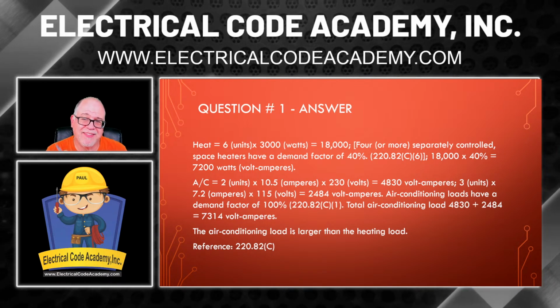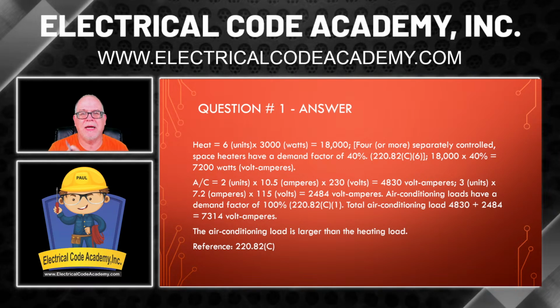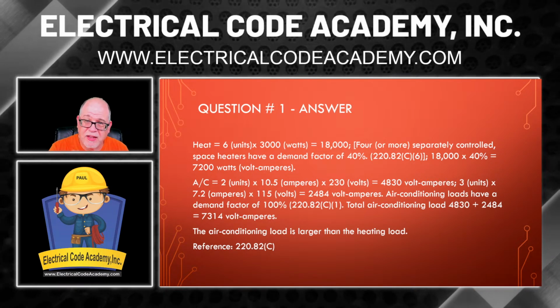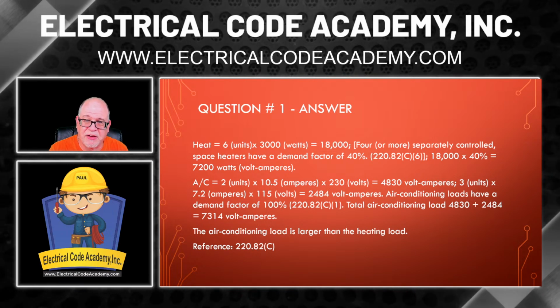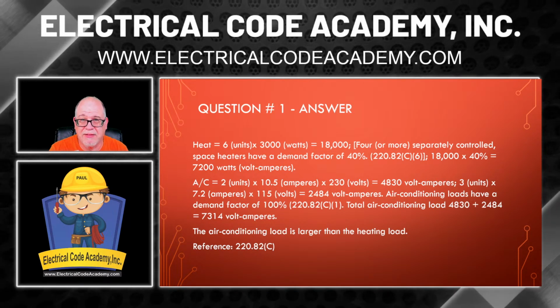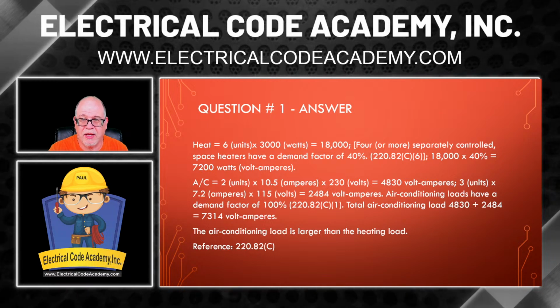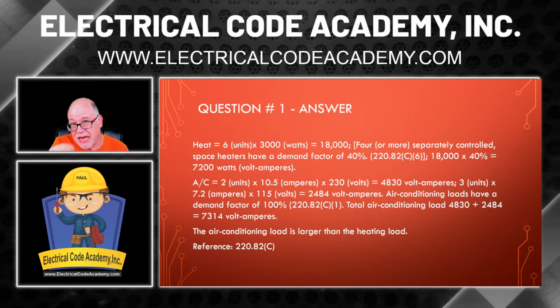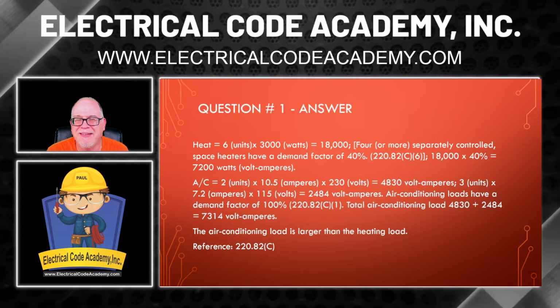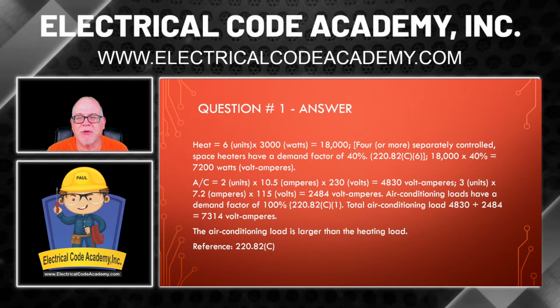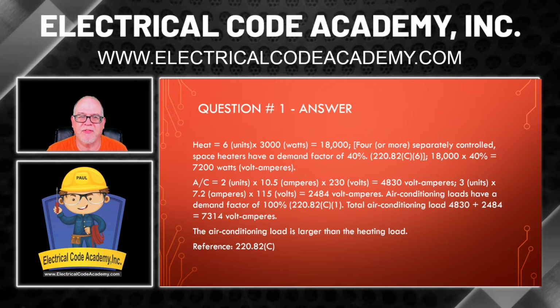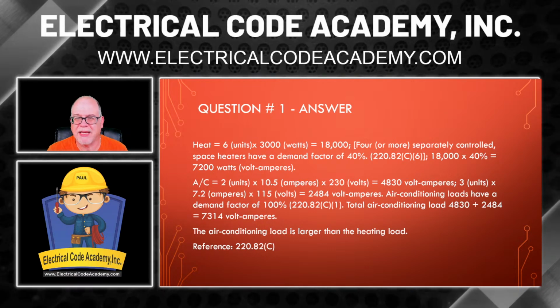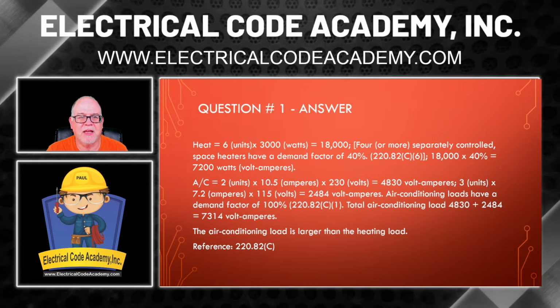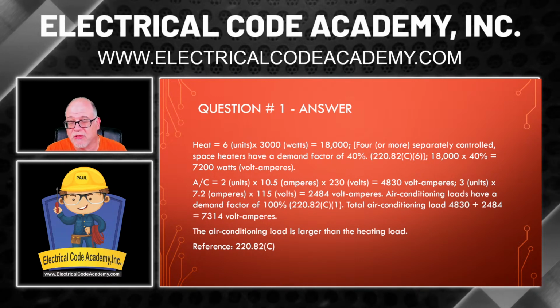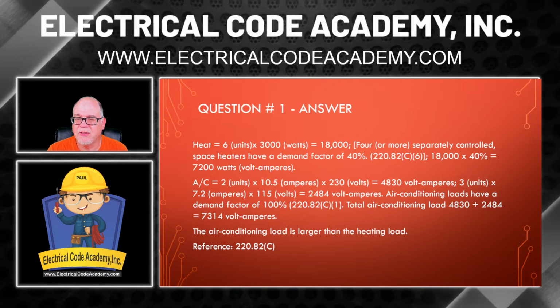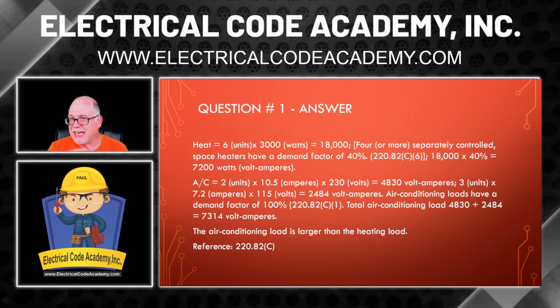Now, remember what it said? It says that we take what? Now, this says 220.82C6, but it's actually, which one was it? It was 5 that we're using for the heat. Okay, so typo. So we're doing 18,000, and we're going to multiply that by 40%. And that gives us 7.2 kW, or in our case, since we worked it out in watts, it is 7,200 watts, or 7,200 VA.